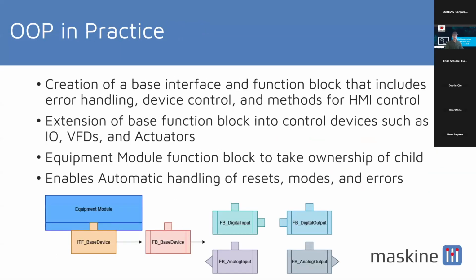By exploiting the object-oriented programming provided by CODESYS, it makes it really easy to handle faults, errors, and device modes for every device in the system. I like to imagine it as a set of locks and keys. By using the interfaces, your equipment module, being the lock here, can take in any key or child device as long as it has that same base device interface. So this lets me pass errors automatically between any of the child devices and the equipment module. It lets me handle all of the resets and mode controls as well. Any time I need to switch from auto to manual, good to go. I don't even need to worry about it anymore.